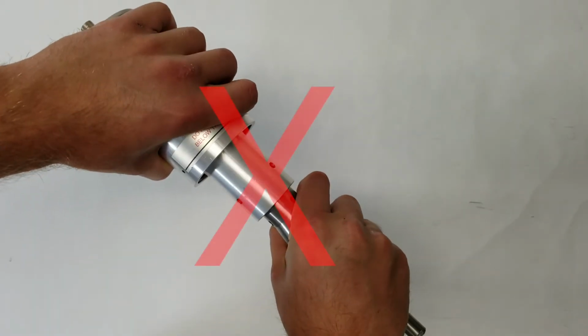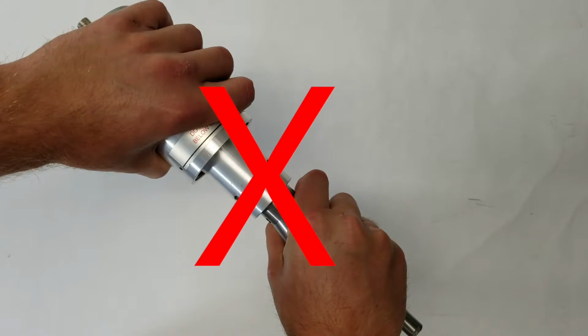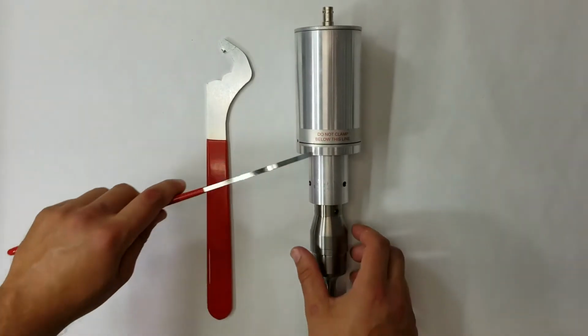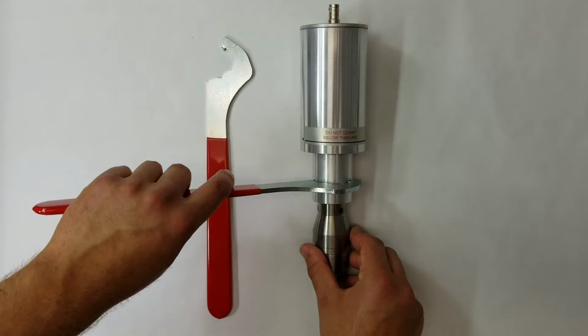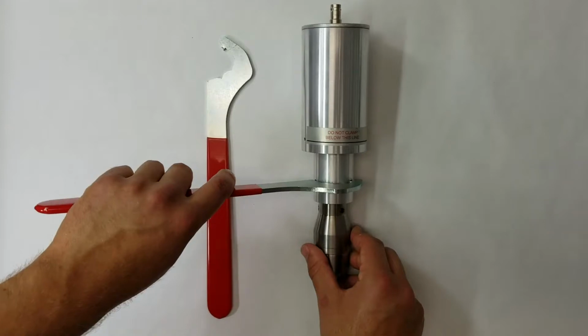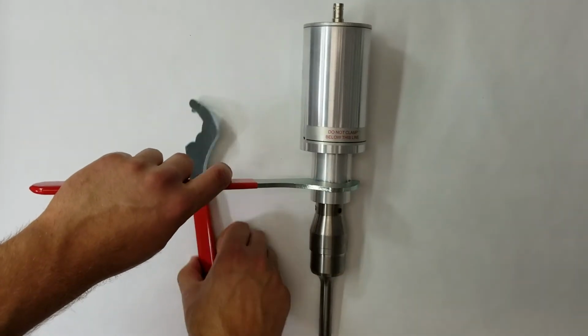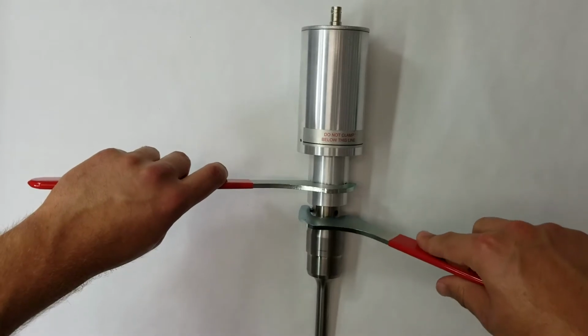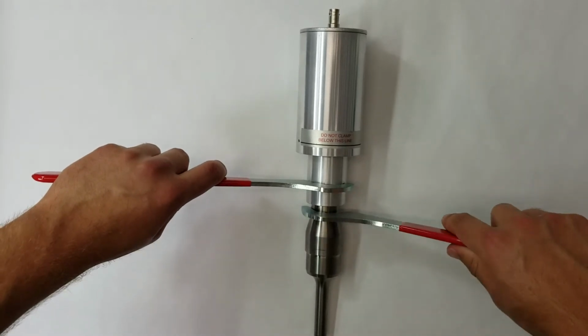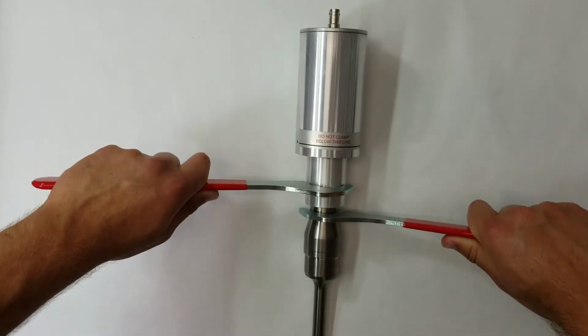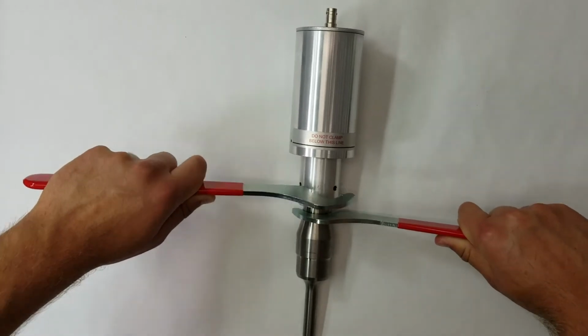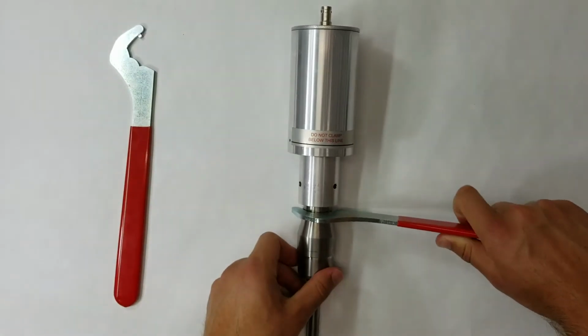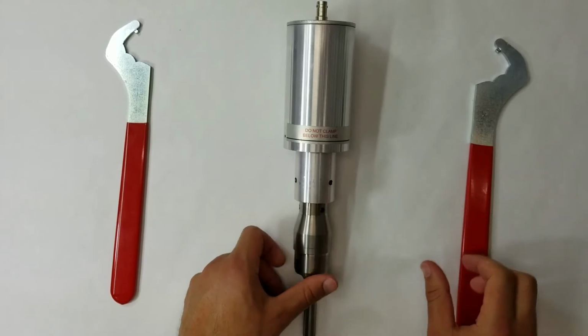Never attempt to fully tighten the probe to the converter just by hand or using only one wrench, as you could damage the converter. Always use 2 wrenches. Once the probe is hand tight, place the engagement pin of the first wrench in one of the holes in the converter. With the other hand, take the second wrench and place the engagement pin in one of the holes in the probe. Tighten the assembly as hard as you can. You won't break the components. Now the assembly is ready to be connected to the power supply.